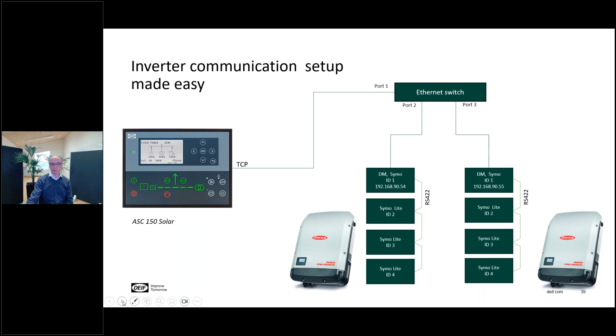In the DEIF free of charge utility software, we can select the application setting here on the left hand side and go to PV Setup. What you need to do is enable the data manager of the first node here and the data manager of the second node, add the IP addresses, and then TCP type is the control type. Add the number of inverters at each node, which was 4 in my example, and then you have more or less set up the communication system for the TCP.